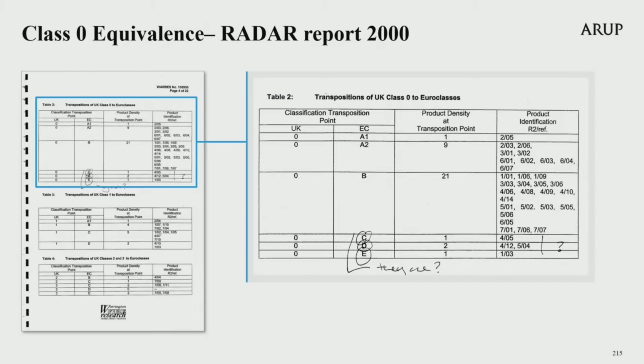I do not understand the purpose of testing 3 mineral wool insulation products, nor the cellular plastic insulation for Class 0, as this was not the relevant performance requirement, as I've stated earlier. The only cladding panel tested was an FR high-pressure decorative laminate panel.